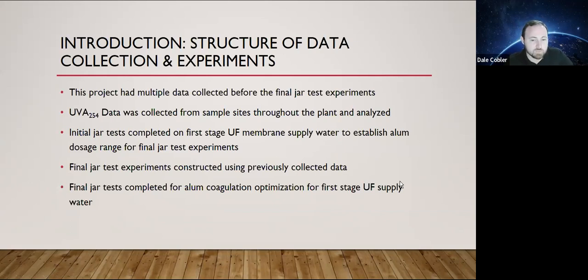This project involved data collection in the TRU water treatment plant that was operating in real time. It was critical to collect as much data as possible to be used for the experiment design and decision-making. The first part of this project focused on UVA 254 data collection to better understand the organic matter that was present at different stages of the treatment. This data was collected weekly, and it was trended to identify if additional organics removal was necessary.